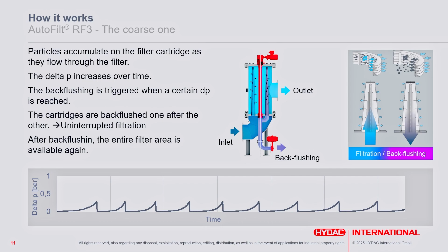Therefore, the gear motor turns the backflushing arm under each element and the backflushing valve opens. By system pressure, it comes to a reverse flow in the element that is being cleaned, and the pollution is carried out of the system. One element is in backflushing, the others still operating. So it is filtrating all the time. Now that you know how this filter works, let us have a look at how the RF14 works and what is the difference to this filter.